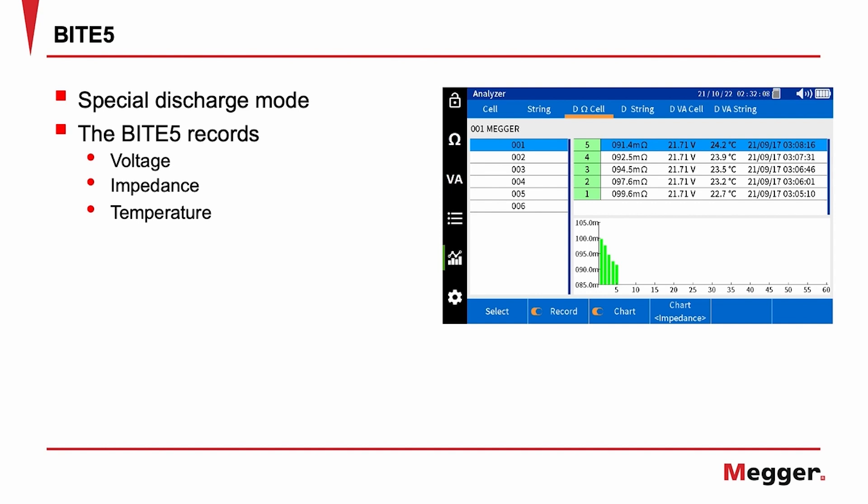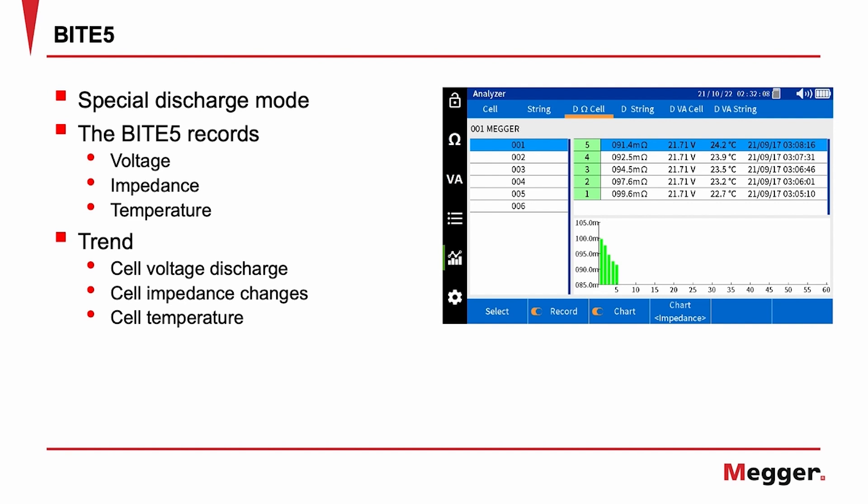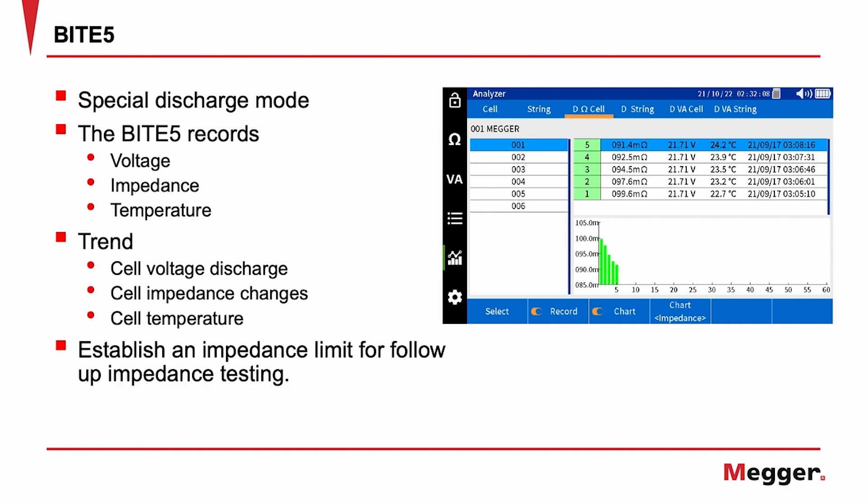The BITE5 can also be used in a special discharge mode. In this mode, the BITE5 will record the cell voltage, impedance, and cell temperature throughout the duration of the discharge test. This allows trending of not only the voltage discharge curve, but the battery's changes in internal impedance and negative plate temperature throughout the test.